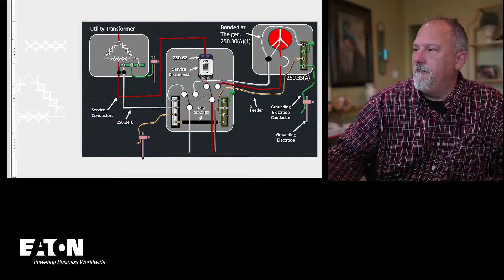I will be talking about the grounding and bonding in the generator and how that goes down to ground when I'm doing a separately derived system. I will be showing and discussing the main bonding jumper that will be in the transfer switch application, how we switch the neutral when we are grounded and bonded as a separately derived system.